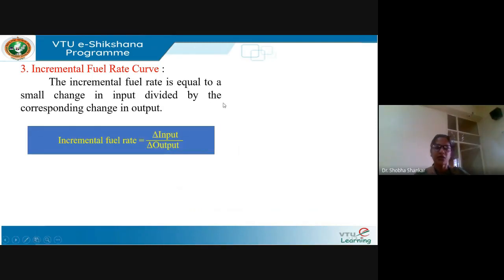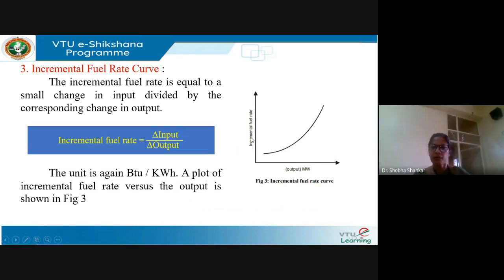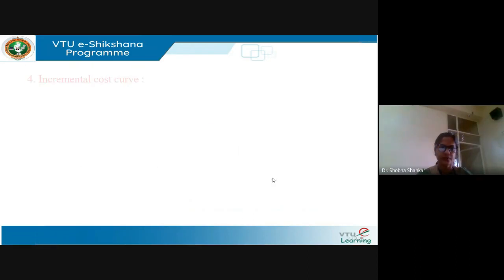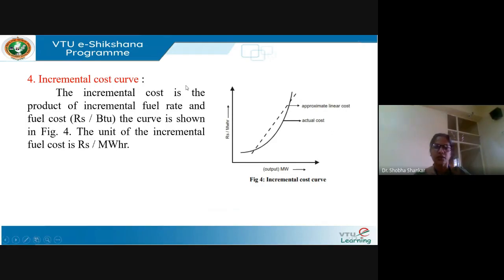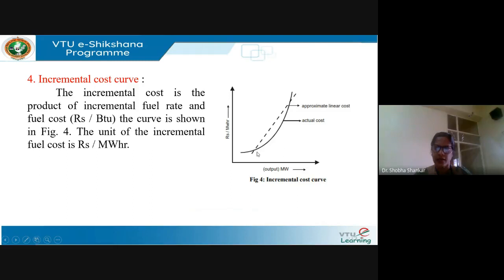The third curve is the incremental fuel rate curve. The incremental fuel rate equals a small change in input divided by the corresponding change in output, with units of BTU per kilowatt-hour versus output in megawatts, as shown in Figure 3. The fourth curve is the incremental cost curve. Incremental cost is the product of incremental fuel rate and fuel cost, where fuel cost is in rupees per BTU. The units of incremental cost are rupees per megawatt-hour versus output in megawatts. This actual cost is non-linear, and this non-linear cost can be approximated as linear, as shown by the dotted line.